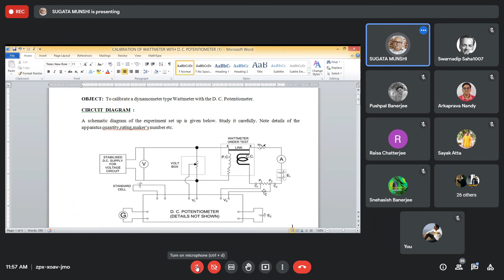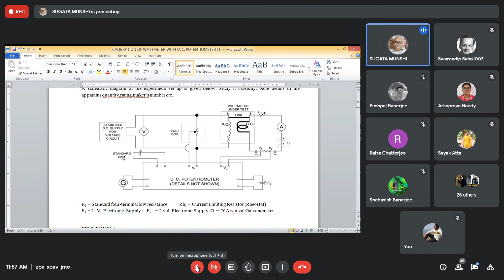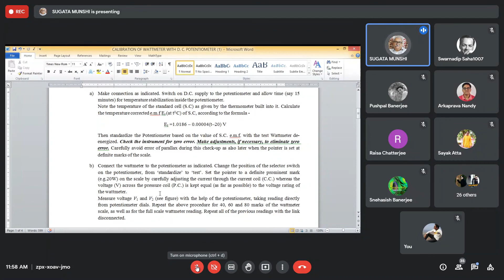A voltage ratio box, the wattmeter itself, a standard low valued resistance - I have mentioned the rating is 0.1 ohm, 15 ampere. DC potentiometer is another thing, D'Arsonval galvanometer, and this is electronic supply. Don't write it as simply standard cell, write it as electronic version of standard cell. And you have to complete this table.